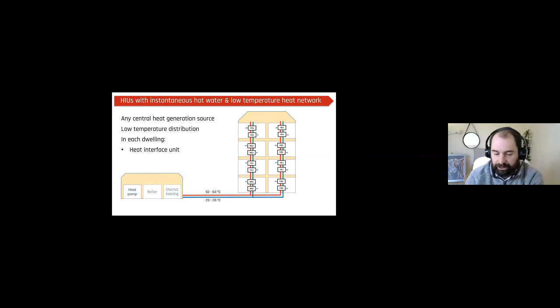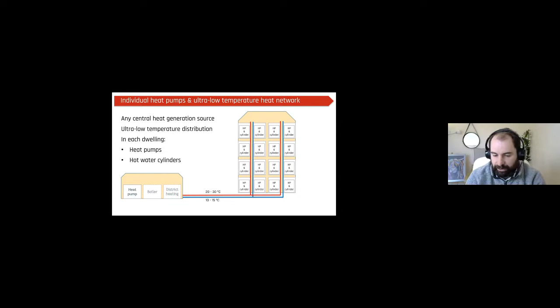So a pictorial representation of that is, this would be a fourth generation system. You have the central plant, which could have heat pump, boilers, district heating, distributing at about 50 to 60 degrees into the buildings with HIUs, and then returning at 20 to 30 degrees. Each flat would have an HIU generating hot water instantaneously. And then for a fifth generation system within a building, it would be again the same central plant, heat pump, boilers, district heating, generating the heat, and then that would be boosted up to the required temperature within the dwelling, and the hot water would be stored in a cylinder within the dwelling.